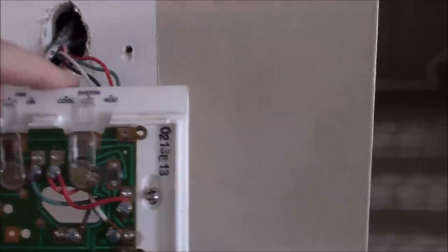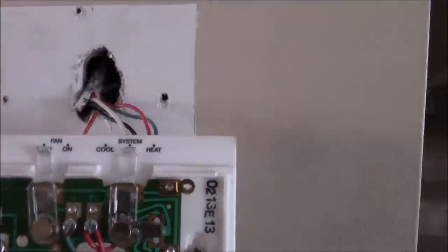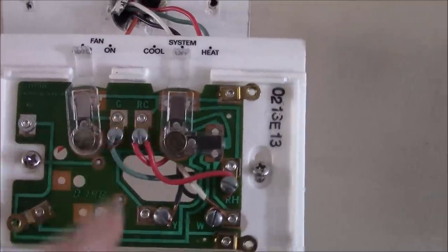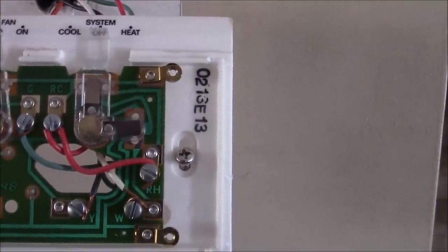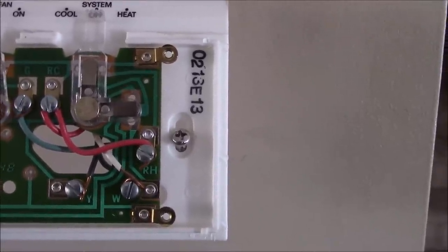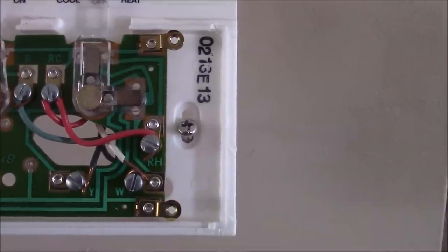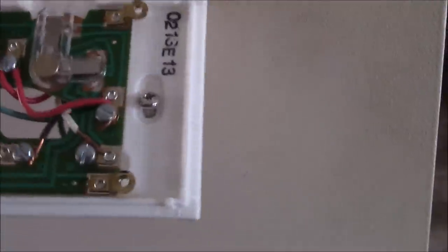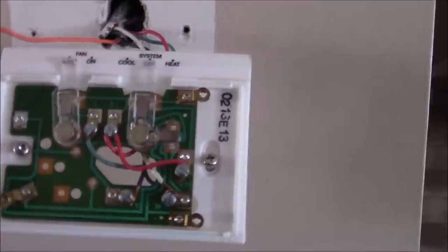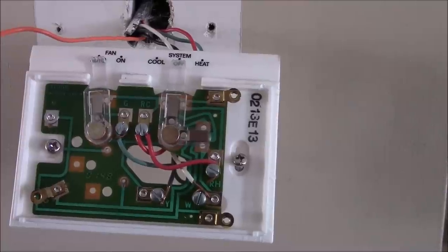This is the old thermostat. It's a four-wire system: black, white, green, and red, going to the corresponding letters. I've got G, RC — looks like I've got a jumper wire — and then RH, W, and Y. The new one is a five-wire system; it needs a C wire, which is the dedicated power wire. Luckily, when I pulled it apart, there was one tucked inside.